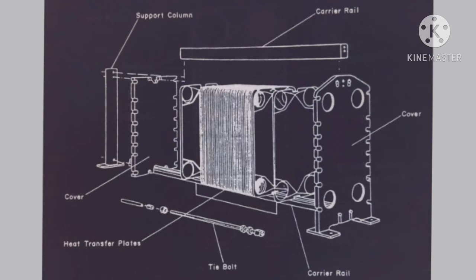We need careful dismantling and assembling. Another disadvantage is over-tightening of the clamping bolts results in increased pressure drop across the cooler. One more disadvantage is that since the plates are made up of titanium, which is a noble metal, other parts of the cooling system are susceptible to corrosion. That covers the disadvantages of plate type heat exchangers.